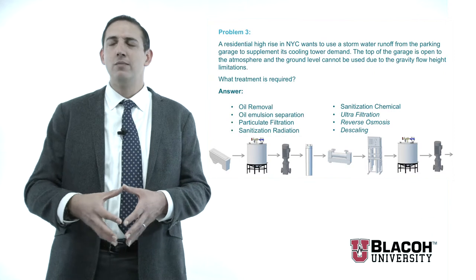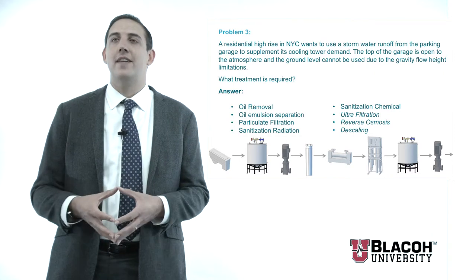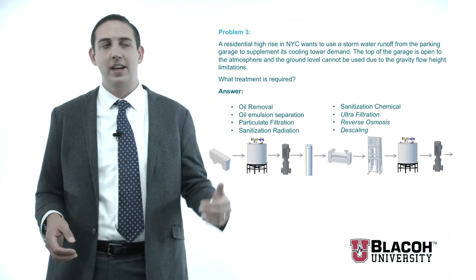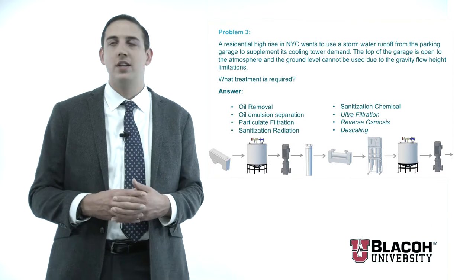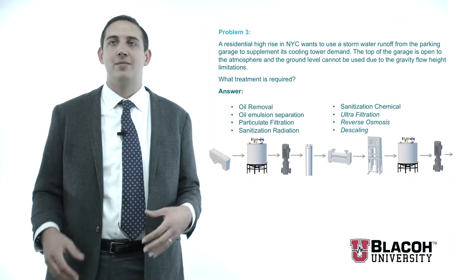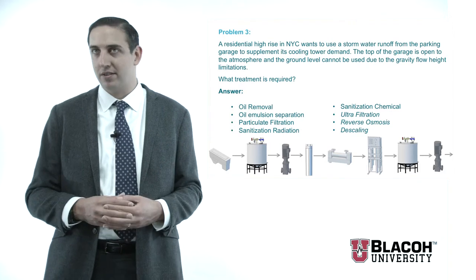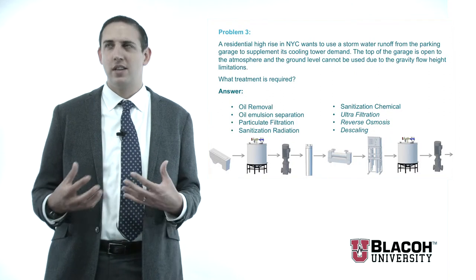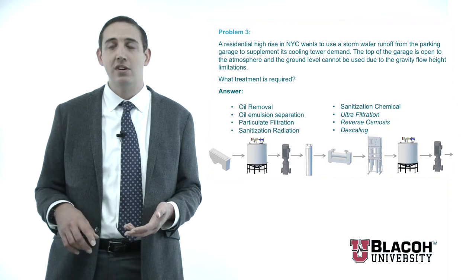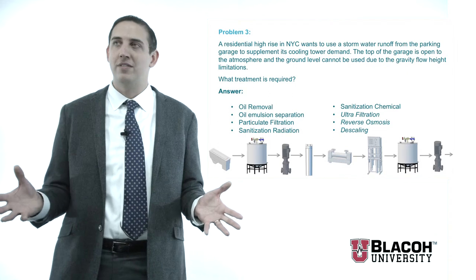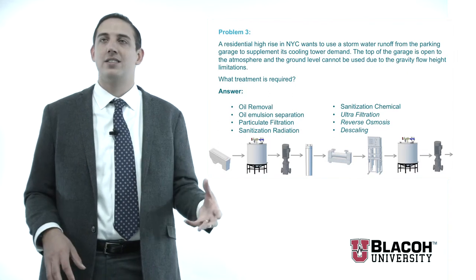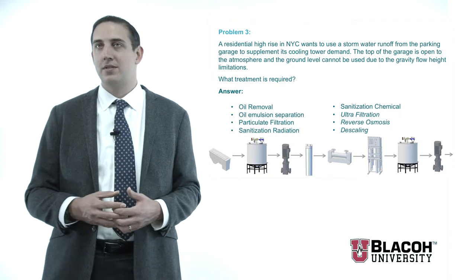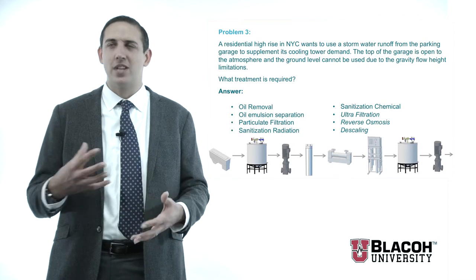We've removed a lot of the heavy particulates, but we still have to get this water disinfected and usable for a cooling tower. Between the cistern tank and clean water storage tank we're going to repressurize the water and use filtration to knock this down to 50 to 10 micron, then go through a membrane-style filter to remove additional contamination — discoloration from spilled sodas, snow melt, de-icer salts — all of that cannot be used in a cooling tower. That will require a low-energy reverse osmosis device; you'll pre-treat and then use RO to do 95% of your cleanup. When you're done, you'll have water that's actually better than city water to supplement your cooling tower.